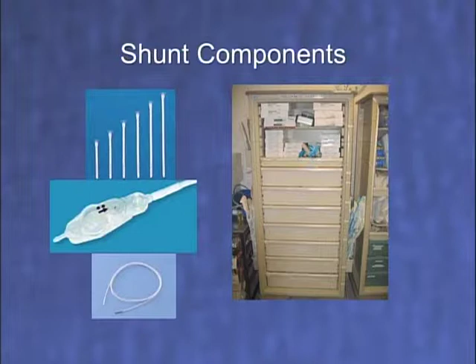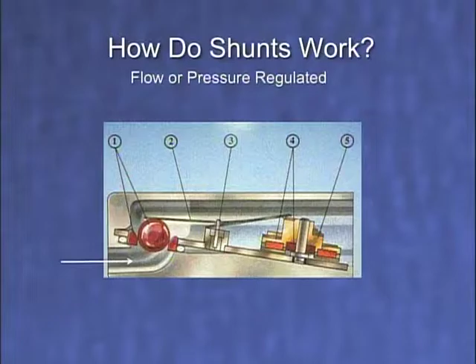So they're called, the majority of them, differential pressure valves. So you get to a certain intracranial pressure with the fluid that allows the valve to pop off and start to flow. This is an example of what's called a programmable valve. So there's an artificial ruby bead that has a lever on it. Once you overcome the force that you set it at, the fluid goes around the bead and then through the valve and then out the tubing to the abdomen and gets reabsorbed. We use programmable valves. There's also non-programmable, meaning that they're sort of set within a fixed range.